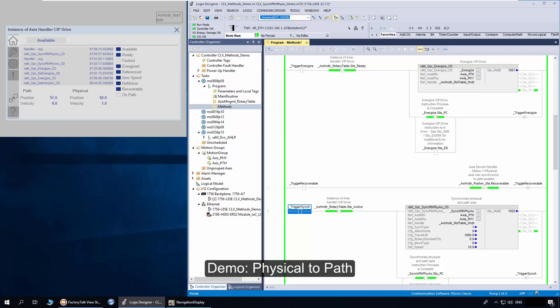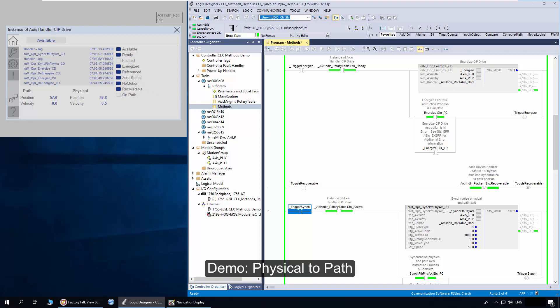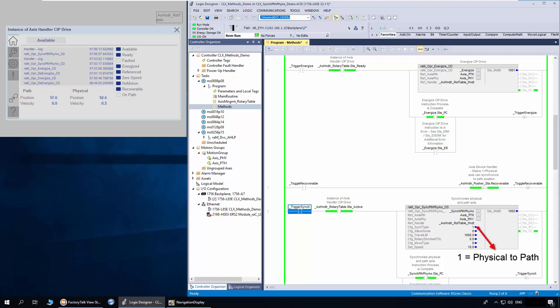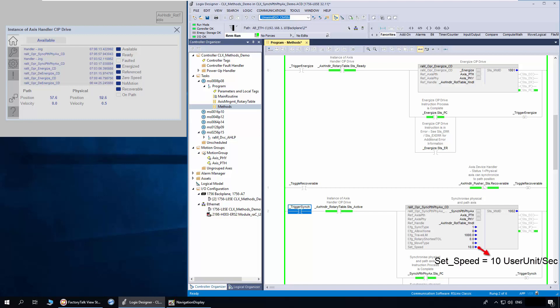Next I will demonstrate physical to path axis recovery. The physical axis is at 92 degrees and path axis is at 57. The sync type is set as 1, which is physical to path axis recovery. Move type is set as absolute. The set speed is at 10 degrees per second.